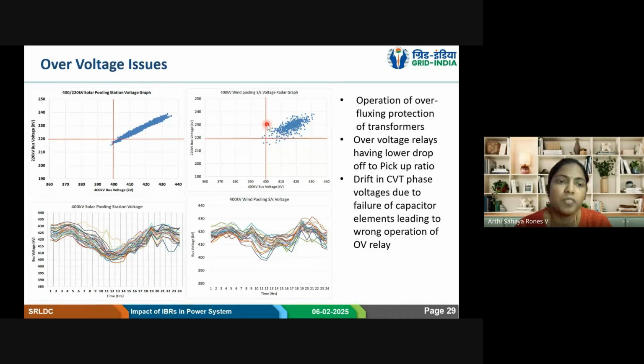Because of this, on the 400 kV side, for the lines we have graded over voltage protection. And for 220 kV lines, we don't have over voltage protection. We ask everybody to disable it. The 220 kV over voltage protection is taken care of by the overflux protection of the transformers only. Sometimes that can also maloperate if the settings are not kept in order as per the design.